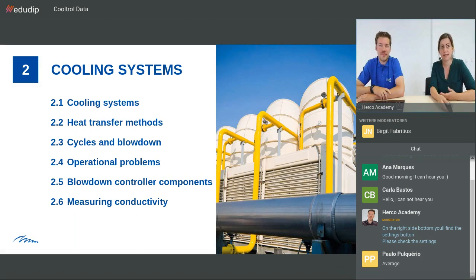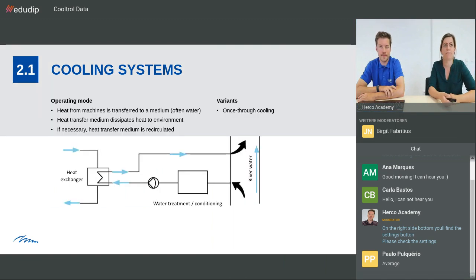Okay, so we'll start off with cooling systems in general. What is it all about? How does the heat transfer work? There are different methods. What are cycles of concentration and what is blowdown really? And which operational problems do we encounter in cooling towers? Then we're going to have a look at what constitutes a blowdown controller, all the components of the cooling tower and the blowdown controller that can interact. And we're going to also have a look at how conductivity is measured in the blowdown controller.